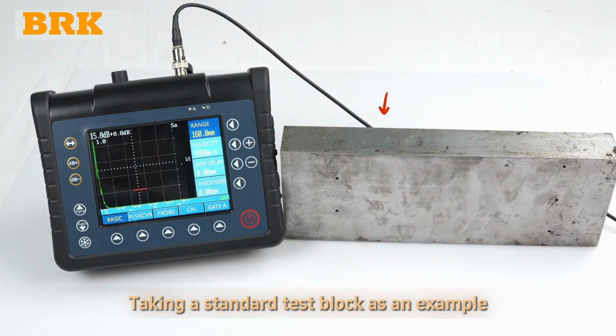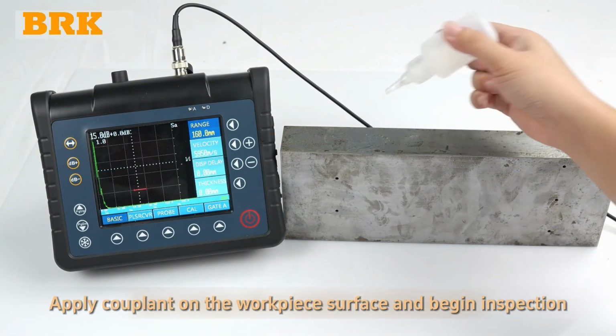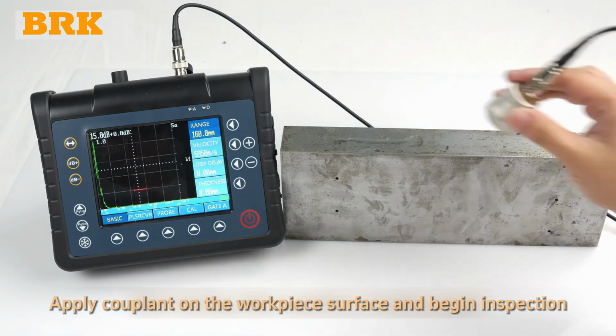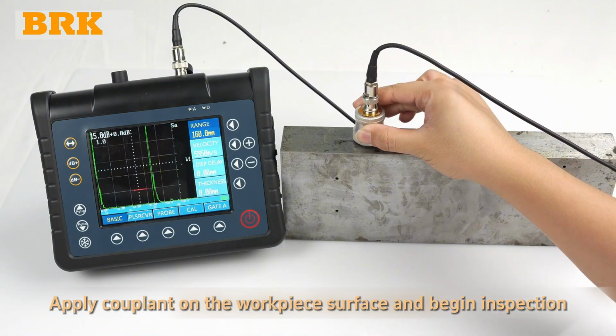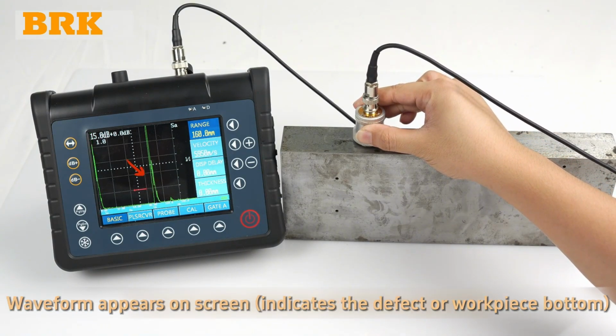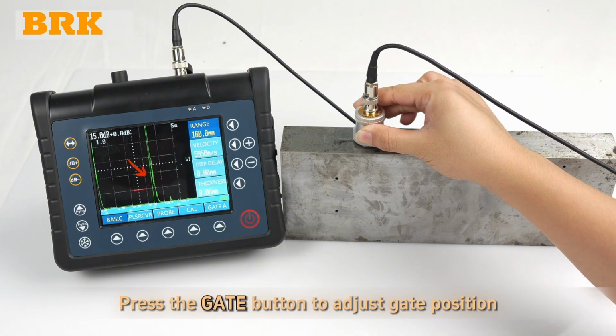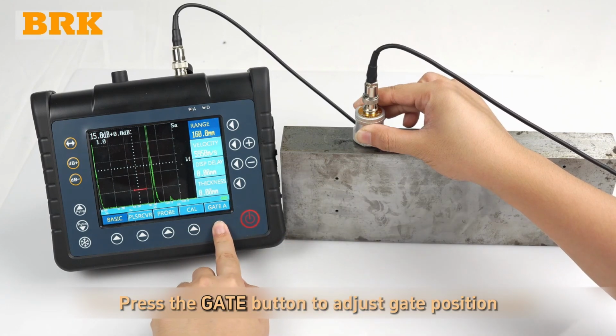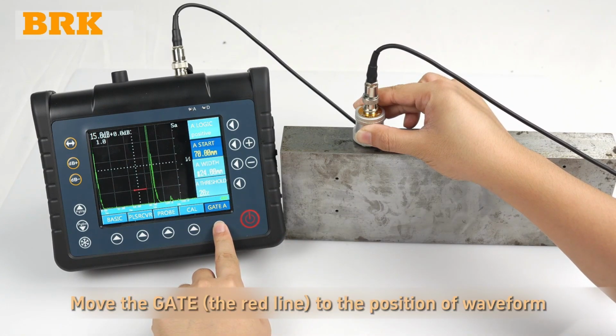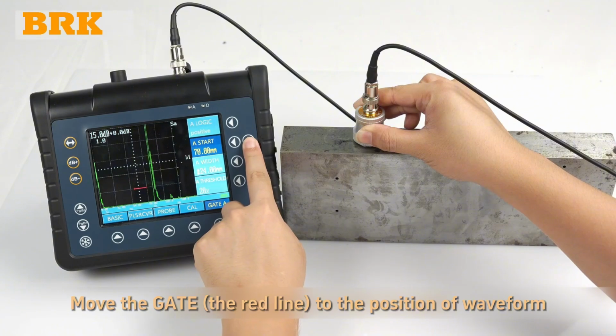Taking a standard test block as an example, apply couplant on the workpiece surface and begin inspection. Waveform appears on screen indicates the defect or workpiece bottom. Press the gate button to adjust the gate position. Move the gate to the position of waveform.